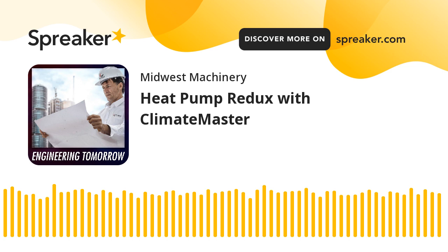Again, we want to maintain that system loop within our operational range between 60 and 90 degrees. So since we're lowering that temp, we want to make sure it stays above 60 degrees. So what are we doing? We're turning on that boiler when necessary. So the controls are monitoring the temps, the flows, and everything else. As those heat pumps are operating in heating mode and dumping cooler water back into that system, we're dropping the temps of the system and the boiler's kicking on to maintain those temps and keep it above 60 degrees.